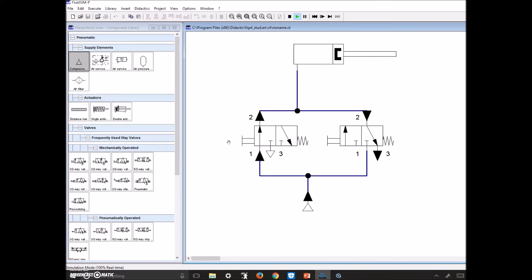But you may have seen the problem with this circuit here. As soon as I hit this button—so let me shift and hit this button—you can see that the air is going up and going to my single acting cylinder, but air is also coming over here and going from two and exhausting out of three on my other push button. Well, that sucks because now I may not have enough air to actually make this go out, and now I'm losing air over here.